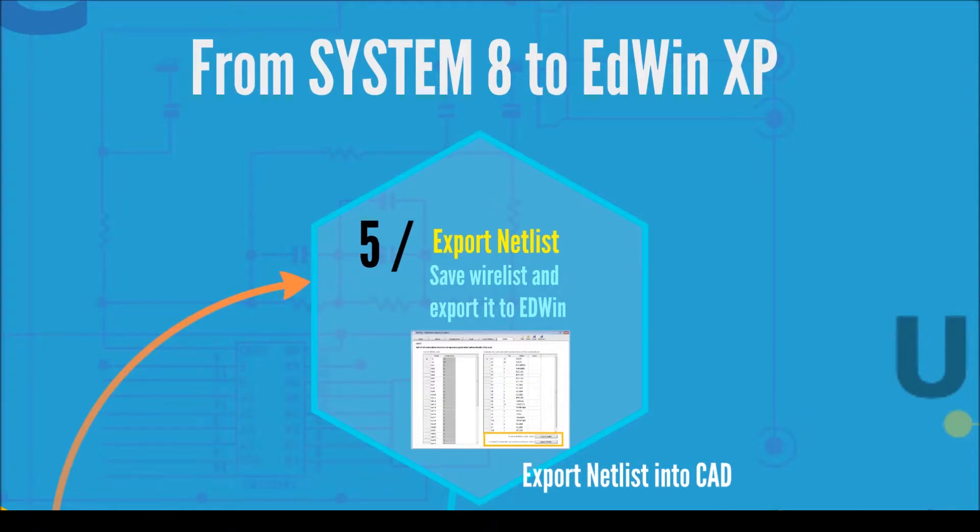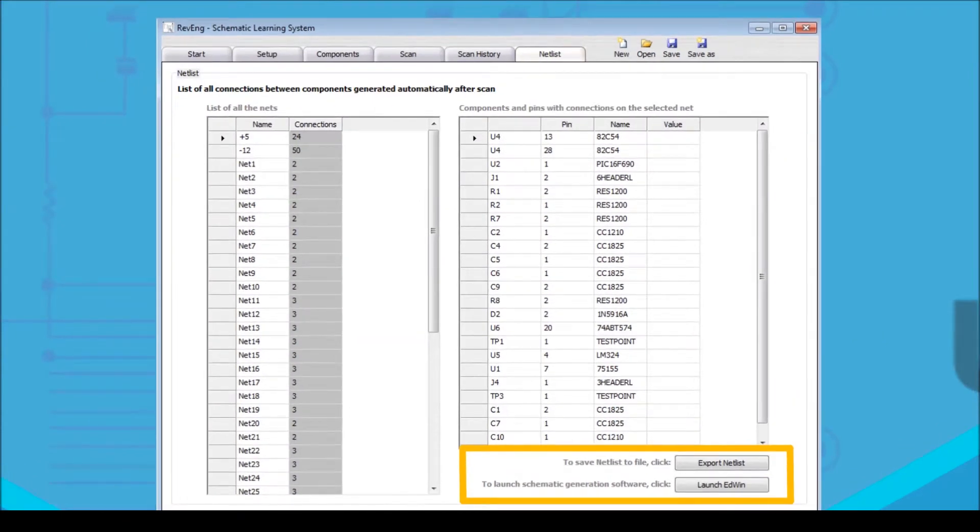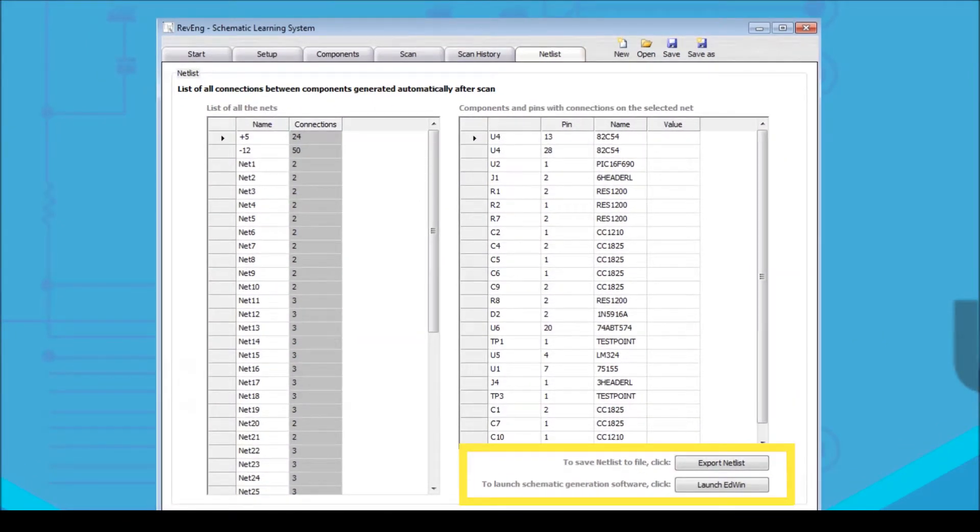Once the system finishes scanning the PCB, a detailed netlist will be displayed in the System8 Ultimate software. When ready to proceed, click in Export netlist to save it as a text file.